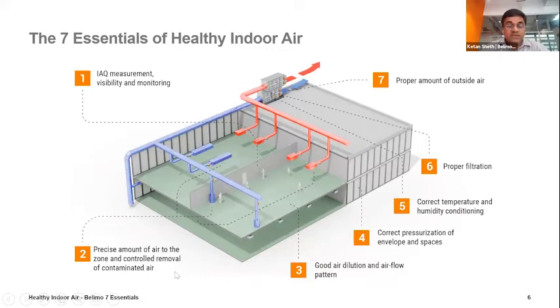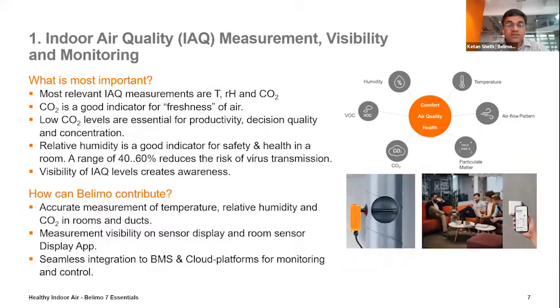The second is the precise amount of air to the zone and the controlled removal of contaminated air. The third parameter is good air dilution in the airflow pattern, the number of air changes, and correct pressurization of the envelope and spaces, which we have also seen and heard about in most of the COVID hospitals. Similar is the case here, and I will explain why it is also important. Then correct temperature and humidity conditioning, which is also an important aspect for restricting the spread of virus. Proper filtration and a proper amount of outside air. We'll move on to the first one, indoor air quality measurement, visibility and monitoring.